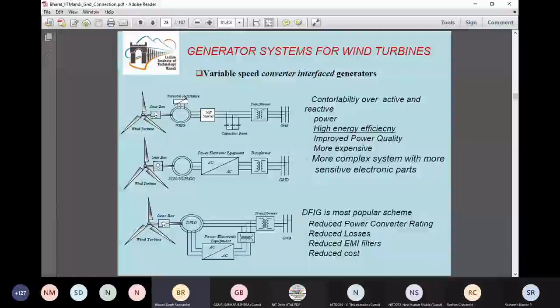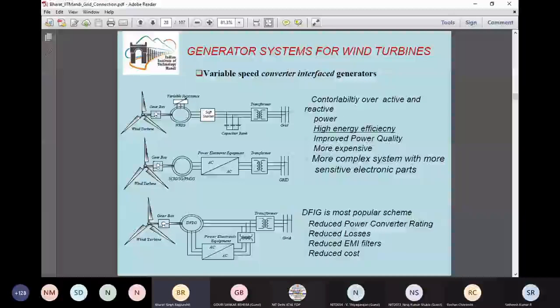This scheme is also very popularly known as the slip power recovery scheme, because as compared to the topmost scheme, there is a difference: in the topmost scheme, a variable resistance dissipates the energy coming out of the rotor to maintain variable speed. But in the below figure, the rotor power extracted from the doubly fed induction generator can now be processed and fed back into the grid. That's why this is known as the slip power recovery scheme, because the power coming from the rotor of the doubly fed induction generator has a slip frequency.